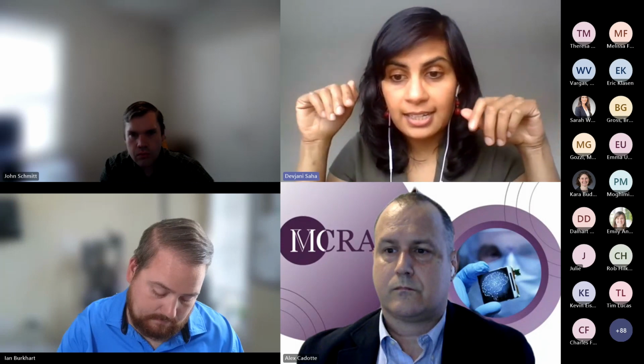Thanks so much, Ian. So hopping over to our next question, I think this one was for me in terms of what is FDA looking for when determining whether the traditional feasibility step can be skipped, right? With regard to that question, there's no rule, there's no mandate that you have to do a traditional feasibility study, right? But one important consideration for an IDE is that for an IDE to be approved, FDA can only look at safety considerations. They're not looking at effectiveness. You might get study design considerations, but your approval of your IDE is really based on safety.